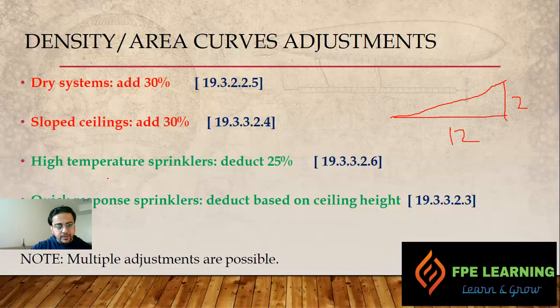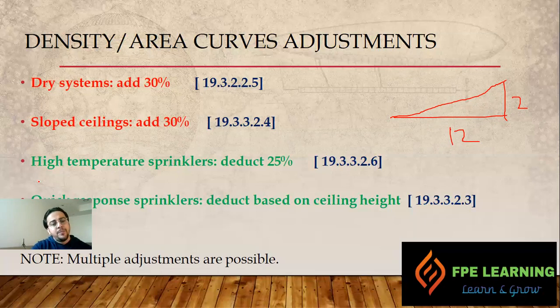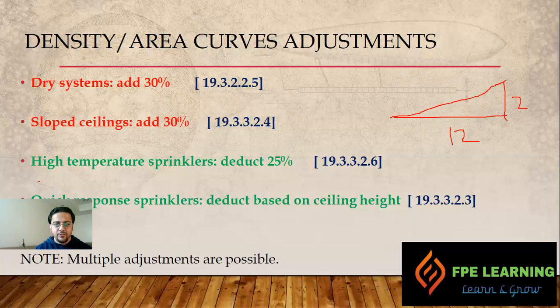The third scenario is high temperature sprinklers, highlighted in green because here we can deduct 25 percent as per NFPA 13 Section 19.3.3.2.6. The reason is that high temperature sprinklers activate fewer sprinklers compared to ordinary temperature sprinklers. Keeping that in mind, we can reduce 25 percent from our design density areas.